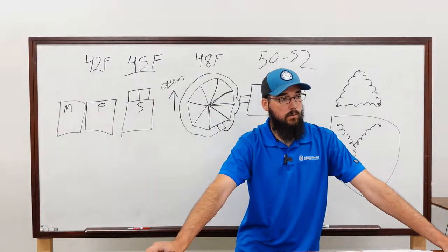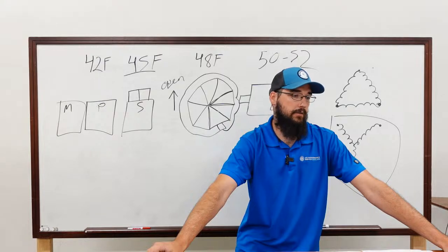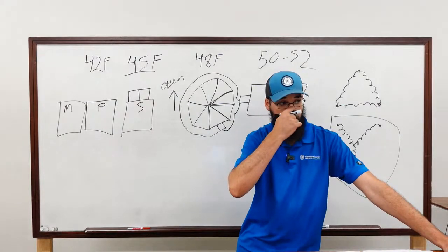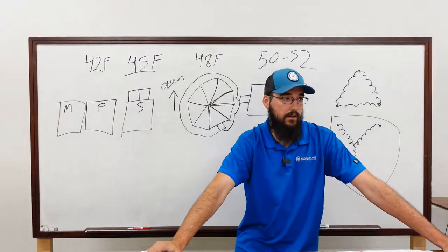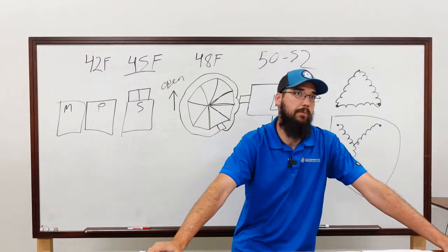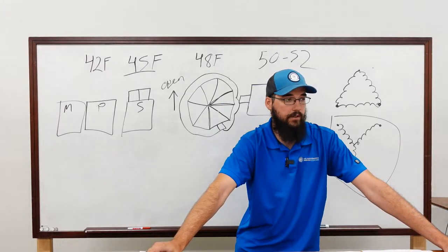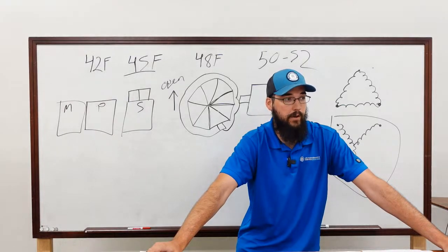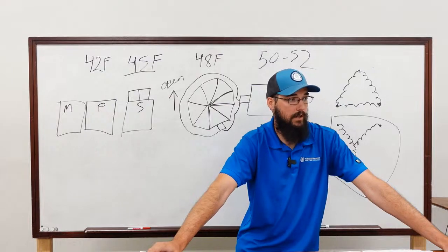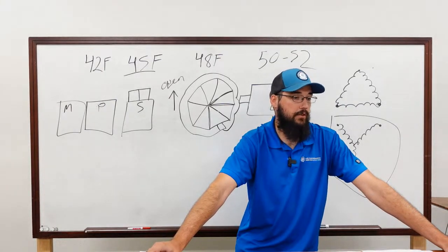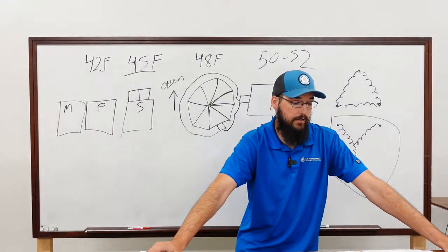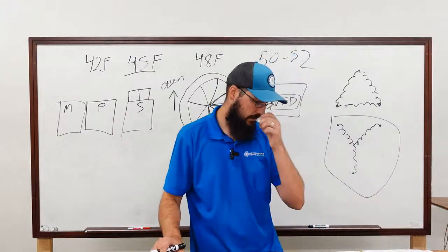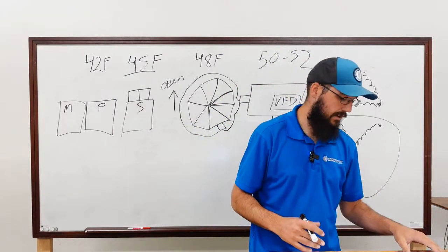I mean, obviously, this is not part of my realm. Well, yet. If you've been around long enough, you had IGVs before you had VFDs inside of air handlers and RTUs. Yeah, the old Trane Voyager systems, before they went to VFD, they used inlet guide vanes. It's the exact same operating theory, because those started with the guide vanes closed, and it kept motor amperage down. Once the motor got up to speed and you needed to maintain static set point on the ductwork, then they would start to open after a delay, and you'd get the static under control. Now we've got VFDs, so we usually go in and lock those guide vanes open on an air handler and just let the VFD do its thing to maintain static. Totally different scenario at that point.